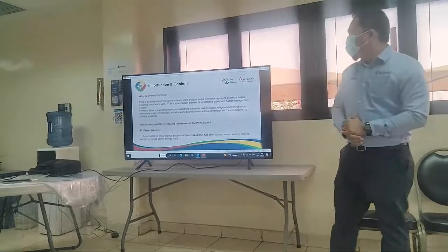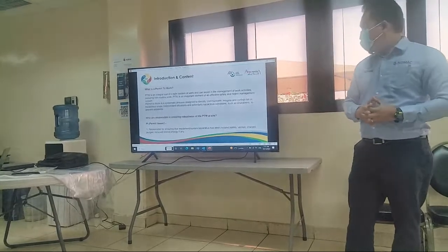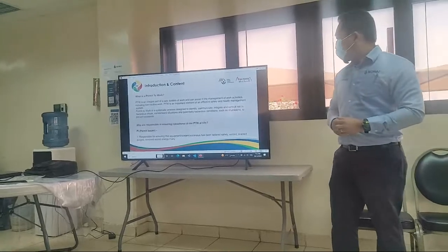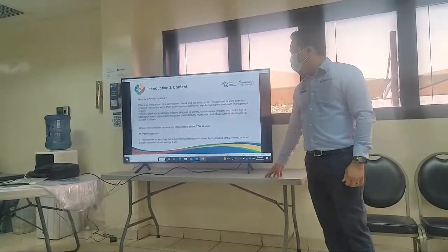Now, the permit issuer is responsible for ensuring the equipment, system, or apparatus has been isolated safely. Through what? How will he ensure that it is isolated? Through his isolation authority, right? Whether the system is being isolated safely, vented, drained, purged, or stored energy removed, if any.